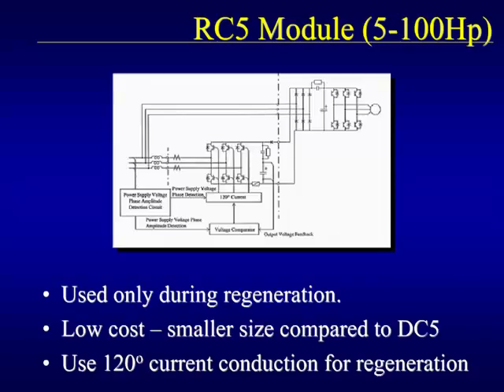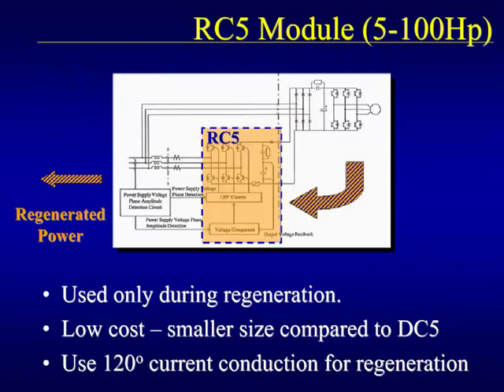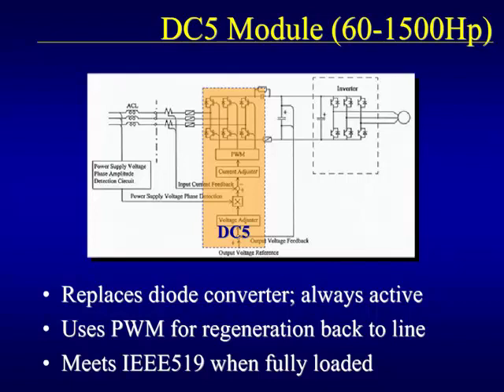Line regeneration modules come in two forms. The first is the RC5, which is connected to both the input power lines and the DC bus of the drive. During normal operation, input power is routed around the RC5 and through the drive's normal converter section. However, as regeneration occurs, the additional power on the DC bus is routed through the RC5 and back onto the power lines. Because the RC5 is not a complete replacement of the drive's converter section, it is a smaller package than the DC5. The DC5 is a complete replacement of the drive's standard converter section — both input and regenerated power are routed through the DC5. The DC5 module is larger than the RC5, but it is capable of handling much larger drive sizes.